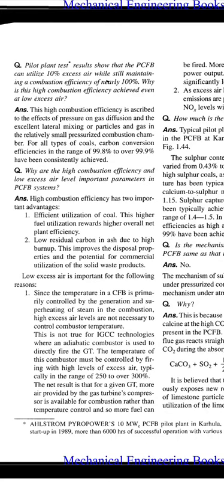This improves the disposal properties and the potential for commercial utilization of solid waste products. Low excess air is important for the following reasons: since the temperature in a CFB is primarily controlled by the generation and superheating of steam in the combustion, high excess air is not necessary to control combustion temperature. This is not true for IGCC technologies where an adiabatic combustor is used to directly fire the gas turbine.